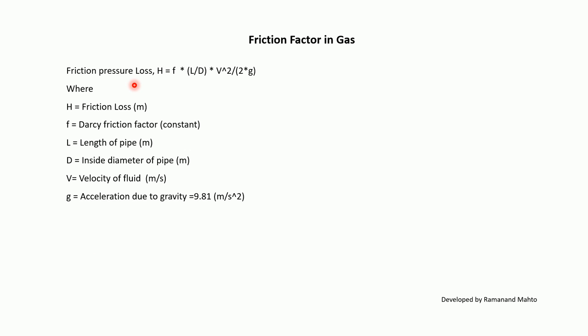Friction pressure loss: H = f × (L/D) × V² / 2g, where H is friction loss in meters, f is the Darcy friction factor, L is the length of pipe in meters, D is the inside diameter of pipe in meters, V is the fluid velocity in meters per second, and g is acceleration due to gravity = 9.81 m/s².